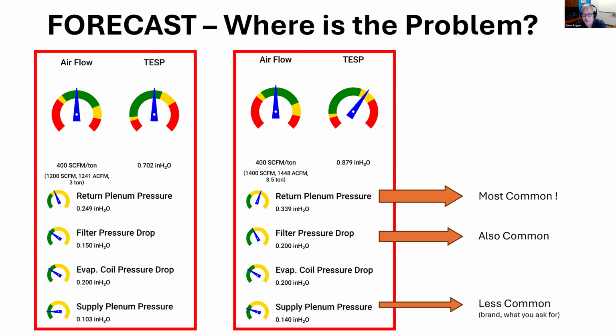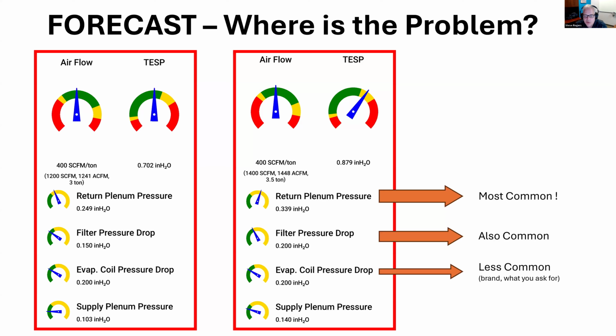Okay, now what about the evaporator coil? That's a less common restriction, but it is still fairly common. And what we find is that the reasons that a brand new evaporator coil would be too restrictive are because it depends what you ask for. If you look through the manufacturer's literature, there may be 3 different coils that you could use for a 3-ton system or for your 3.5-ton system, whichever you're going to go with. But they're not the same size and they don't have the same pressure loss. So if as a technician, you just walk into the supply house and say, I need a 3-ton indoor coil, the one that they give you might be the one that's physically smaller and therefore has a higher pressure loss.